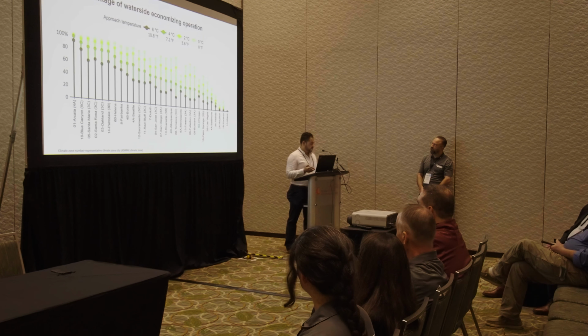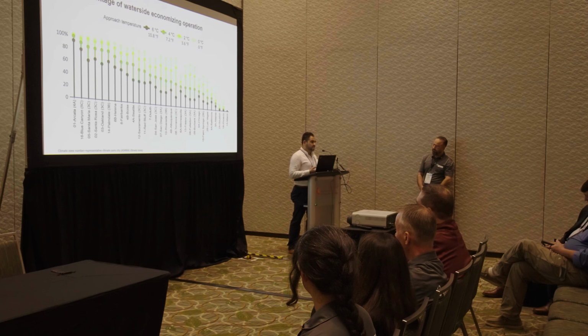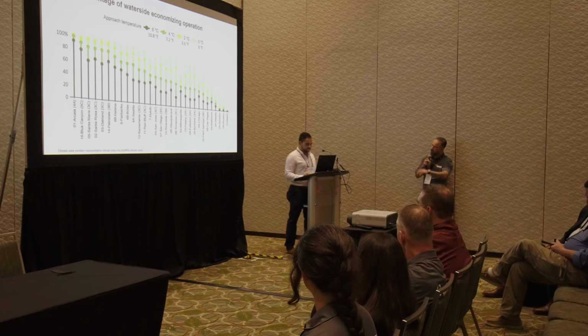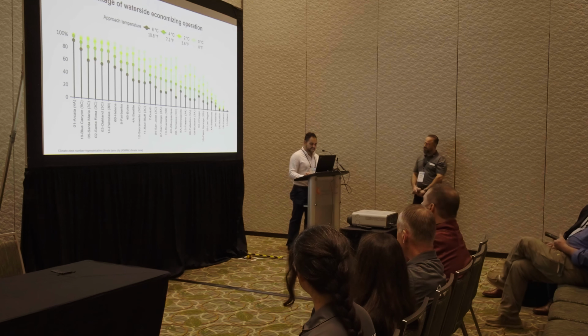Conversely, if we look at the ASHRAE climate zone 3A, which is representative city Atlanta, at least 50% of the models could supply the model's design chilled water only 10% of the time. So there's a big reduction because Atlanta is a hot and humid climate, so there's less possibility to do waterside economizing there. Miami is even worse. Yeah, so Miami, there's 0%.